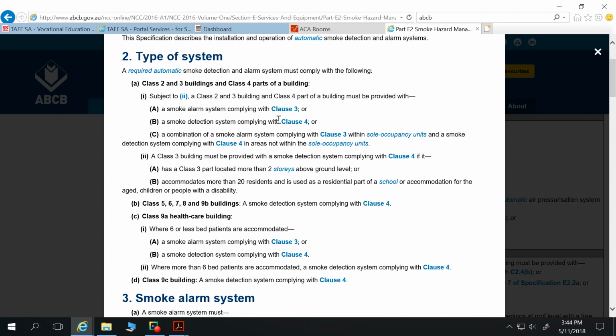So whenever people are sleeping and there's smoke, they need to be told. You need a really high pitched alarm, and those fire alarms have to be interconnected. So if you've got, say, a fire happening in the garage, that tells people in the bedroom that there's a fire happening. With our 5, 6, 7, 8, people are normally awake in the office. So that's a smoke detection system, whereas within these ones they have to be a smoke alarm system, and that's the two differences.